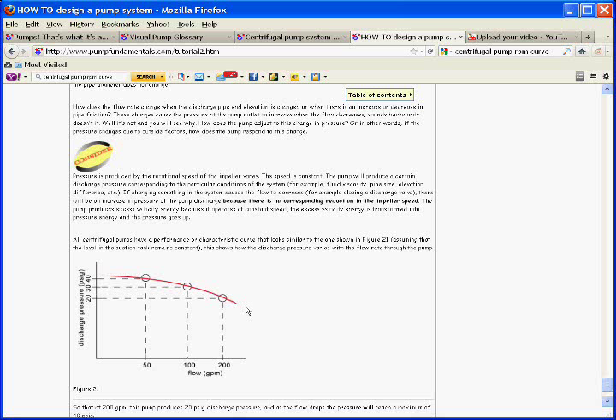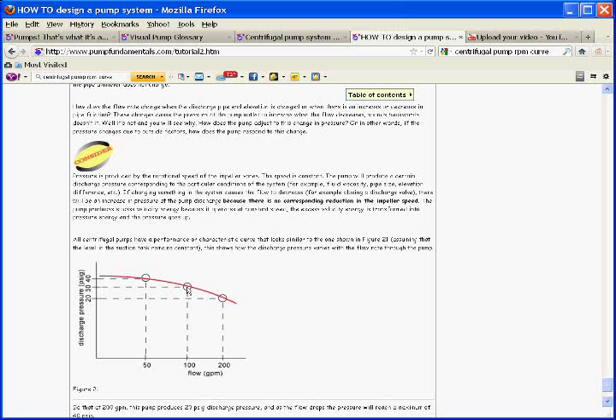I think you'll understand what's happening in a second. If I'm operating the pump at this point here, at a given flow rate, that will require a certain amount of head or pressure. If I decide to close the discharge valve, what's going to happen? The liquid now doesn't have any other place to go because only a portion of it is going out the discharge. There's going to be less liquid coming out. We'll be producing more pressure within the casing because there's no way for all of it to go out. That drop in velocity in the casing doesn't occur as much.